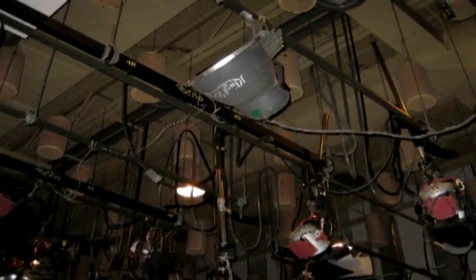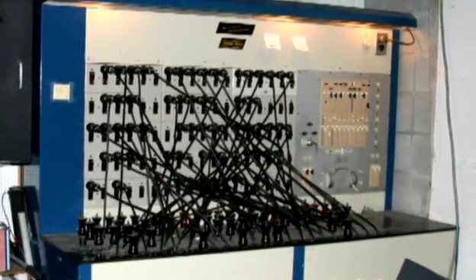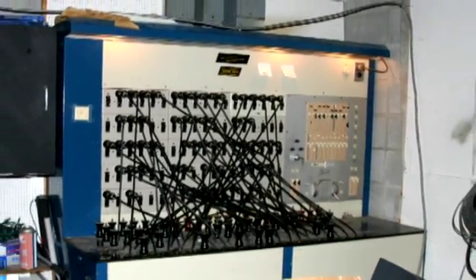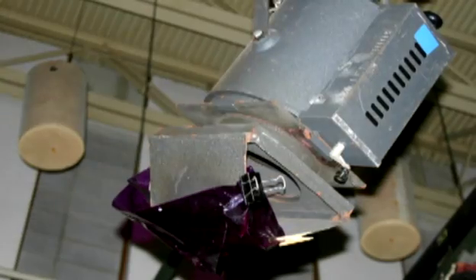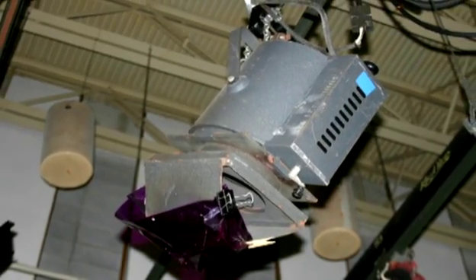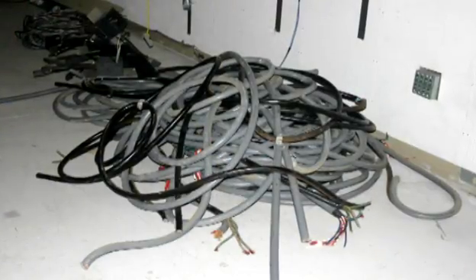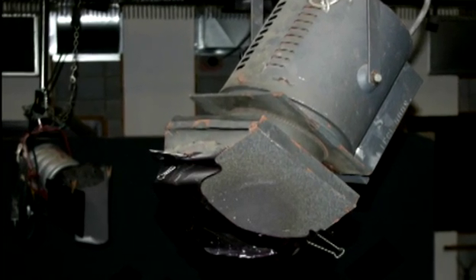At WKYU, we were slowly, over many years, developing a problem with power delivery to our lighting grid. The system had originally been installed in 1969. Wiring was deteriorating and power delivery was inconsistent. We could not simply afford to rewire our studio with the same amount of copper from the original installation. Additionally, our incandescent tungsten fixtures were highly inefficient, and many of the stage plugs connecting them had fused together. So we had to think of an innovative solution.